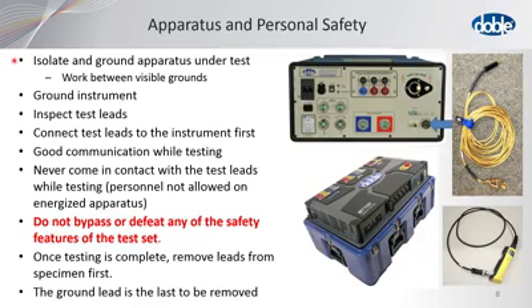In this particular model, if you press it too hard, it will also go off, and it will interrupt the test. And this is so that anyone that maybe gets into the test voltage will tense up and shut the test set off. This is an added test feature that is available for both the M4100 and the M7100.